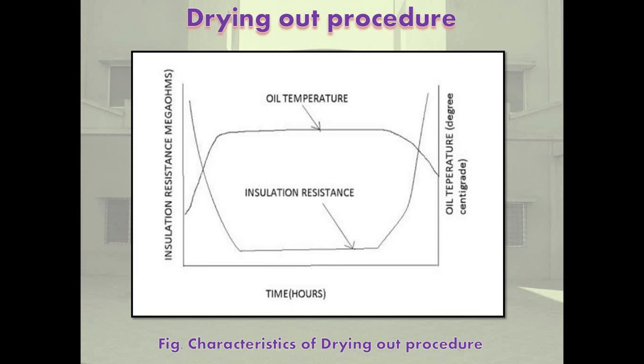The drying out process has three distinct phases, described as follows. First, initially the insulation resistance value falls down, indicating that the moisture is getting released within the insulation. After a few hours, the insulation resistance reaches a steady value, indicating that the moisture has been distributed within the winding. This phase lasts for several hours or days, depending upon the size of the transformer, the amount of moisture, and the insulation resistance. In the final phase, the insulation resistance starts increasing.